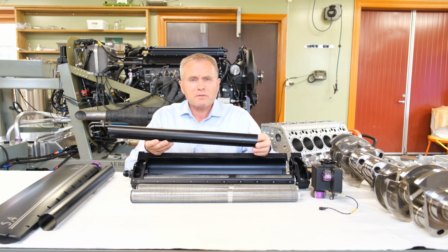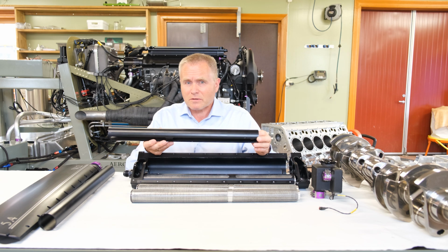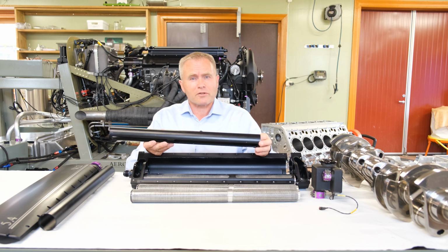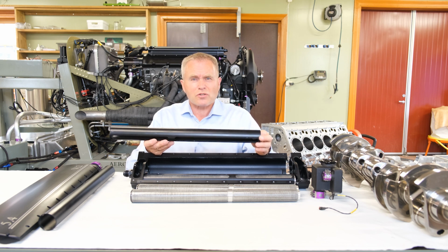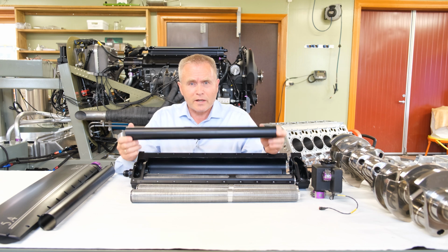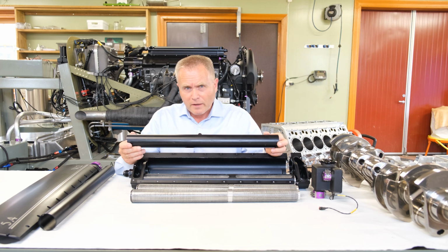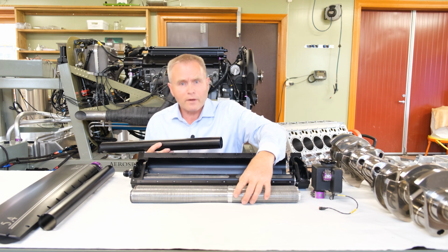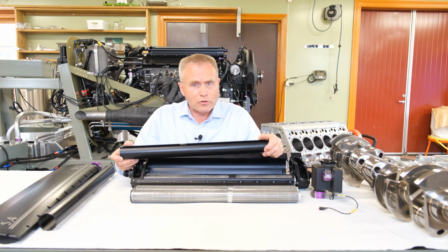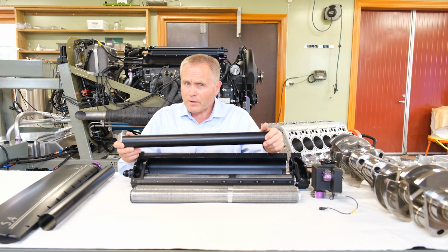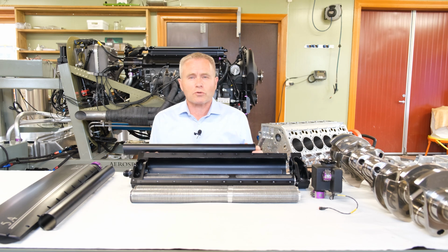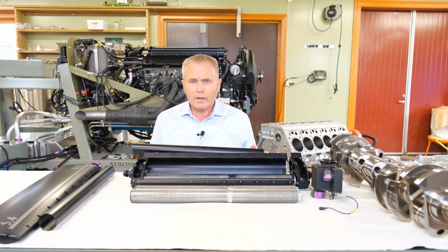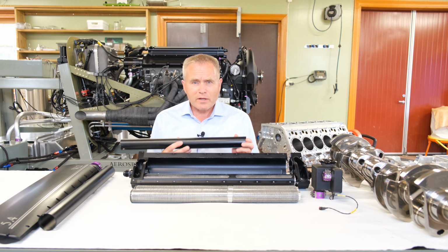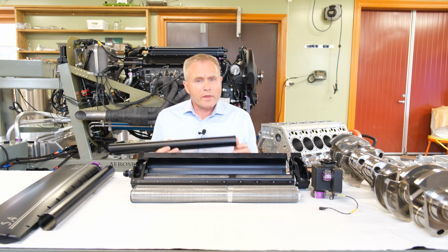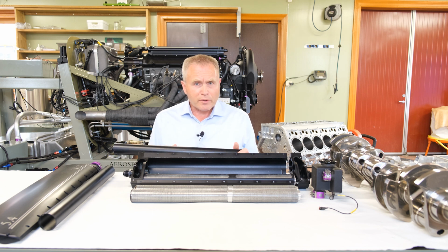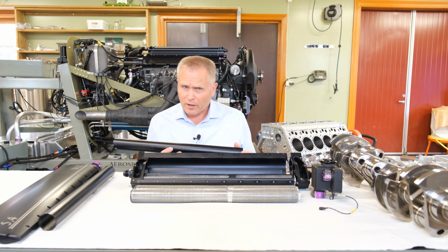At first glance, one may wonder, this must be the point where the engineer fell asleep, right? It just looks like a huge restrictor for the air to flow by. You're probably thinking that the core itself, without the shield around, looks like a big restriction. This is a very interesting topic, so let's take a closer look at what's going on here. First, let's imagine these three cores inside the plenum without the tube or the shield around them, because the tube will actually act like a shield.